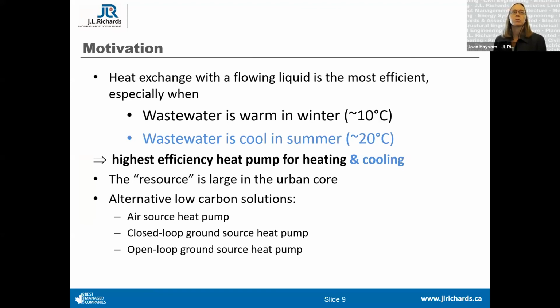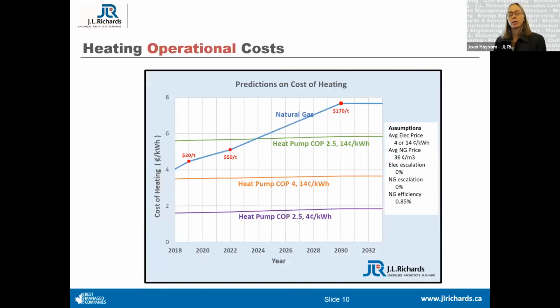So it's quite a high efficiency heat pump, available for both heating and cooling supplies to buildings and district energy systems. We're motivated because the resource is large and well located, being largest within the urban core. The main alternative solutions are air source heat pump, closed loop ground source heat pump, and open loop ground source heat pump. It is a heat pump technology, as I'll get to in a second.